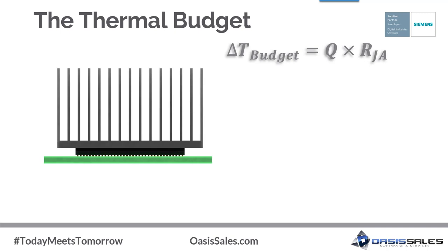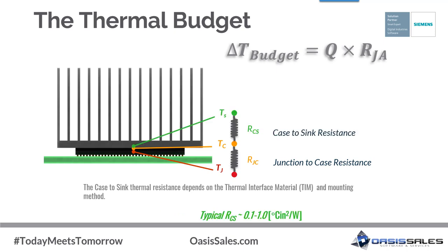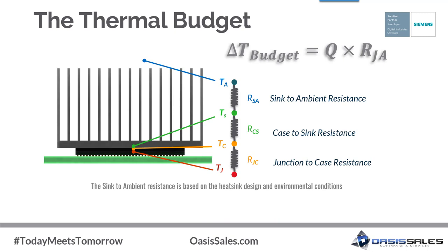The delta T budget is the difference between the maximum allowed junction temperature and ambient temperature. Q is the power dissipation of the device. As a conservative assumption, all heat is assumed to flow into the heat sink base. The first thermal resistance is the junction-to-case resistance; for a typical CPU, this is in the range of 0.1 to 1 K/W. The next is R_CS, case-to-sink thermal resistance associated with the interface material. TIM values are typically presented in terms of bond line thickness and thermal conductivity (L/k). The final resistance is R_SA, the sink-to-ambient thermal resistance, which is a function of the heat sink thermal design.